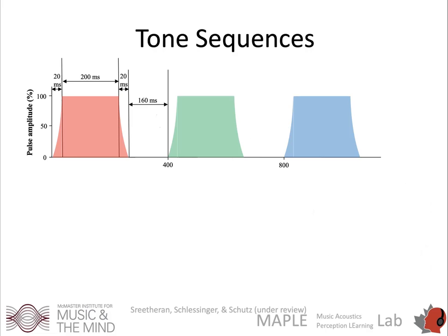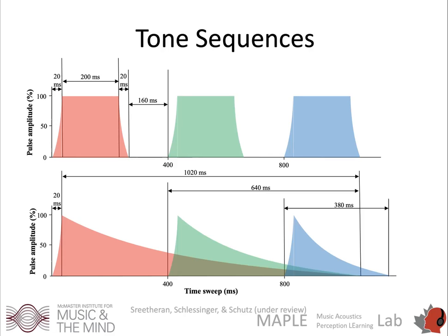The main thing we're exploring here is how the temporal structure can be varied in a way that's a little more patient-friendly. In a typical instantiation of these sequences, we'd have 3 tones that are fairly brief, about 200 milliseconds each, and I'll play you an example of that later on, but we're taking that idea and varying it and making percussive shapes for each individual note. So here each note can be a little bit longer, and they can also blend together, and it results in a very different soundscape.